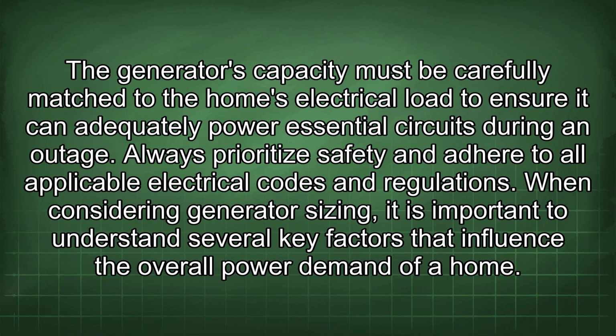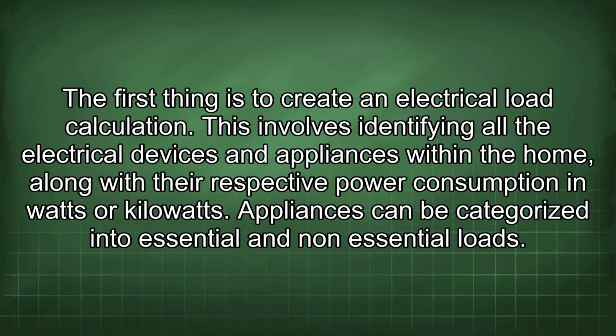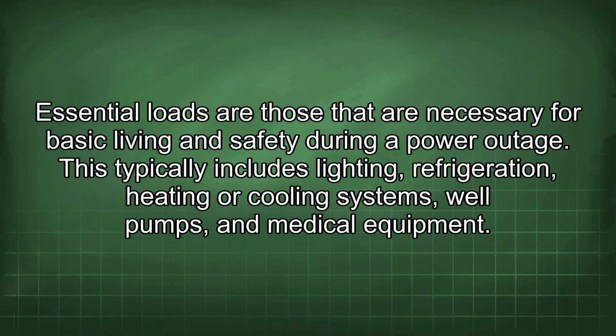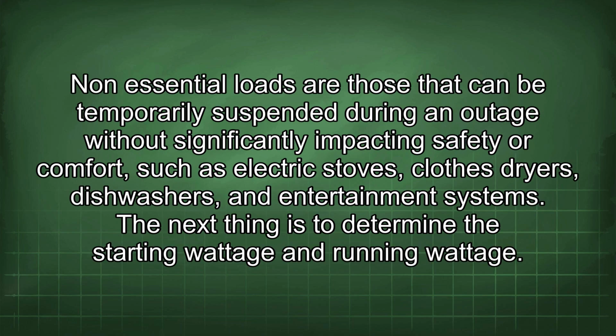When considering generator sizing, it is important to understand several key factors that influence the overall power demand of a home. The first thing is to create an electrical load calculation. This involves identifying all the electrical devices and appliances within the home, along with their respective power consumption in watts or kilowatts. Appliances can be categorized into essential and non-essential loads. Essential loads are those that are necessary for basic living and safety during a power outage. This typically includes lighting, refrigeration, heating or cooling systems, well pumps, and medical equipment. Non-essential loads are those that can be temporarily suspended during an outage without significantly impacting safety or comfort, such as electric stoves, clothes dryers, dishwashers, and entertainment systems.